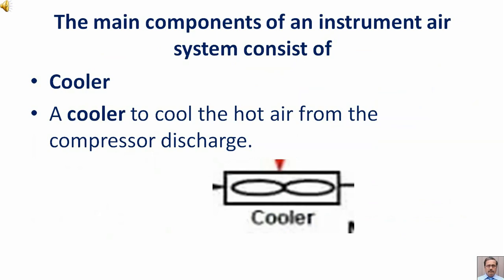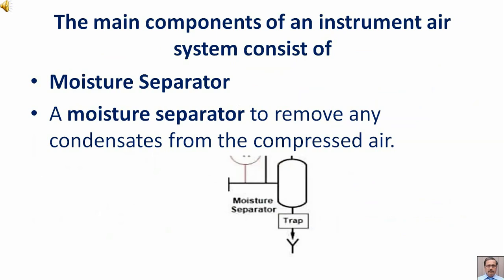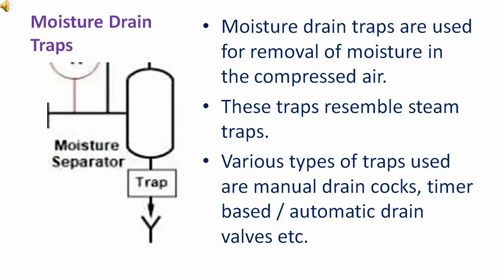Cooler: A cooler is required to cool the hot air from the compressor discharge. Moisture separator: A moisture separator is required to remove any condensate from the compressed air. Moisture drain traps: These are used for removal of moisture in the compressed air. These traps resemble steam traps. Various types used include manual drain cocks, timer-based or automatic drain valves, etc.